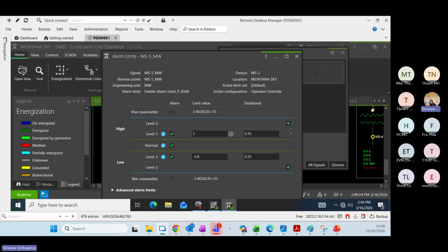Yes, we have, but just for some voltage from the bus bar or voltage for the transformer only. We apply the alarm limits for those volts only, not for ampere. Because our infrastructure's rated power is around 600 ampere for current, but we just run around 300 only, so we have 50% redundant.